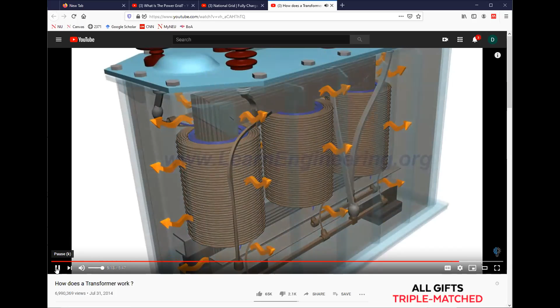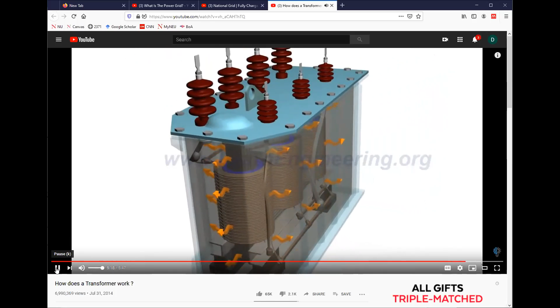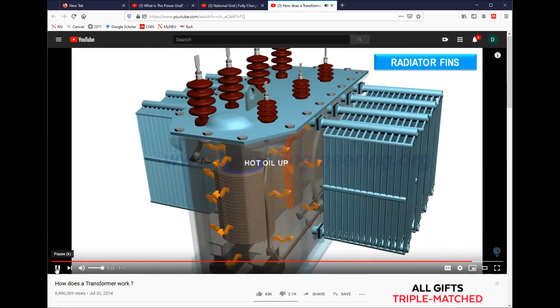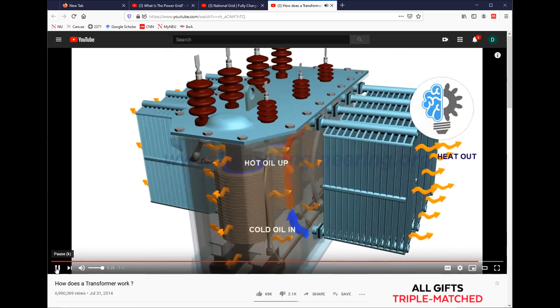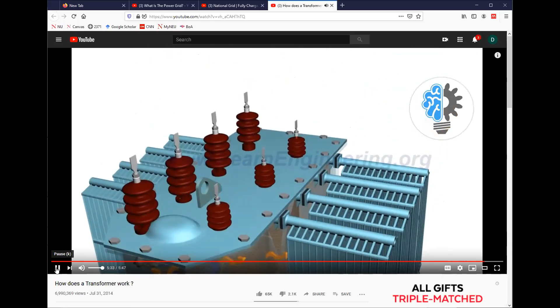Usually the transformer is immersed in a cooling oil to dissipate the heat. The oil dissipates the heat via natural convection. Oil in the tank will expand as it absorbs heat. A conservator tank helps to accommodate for this volume change.